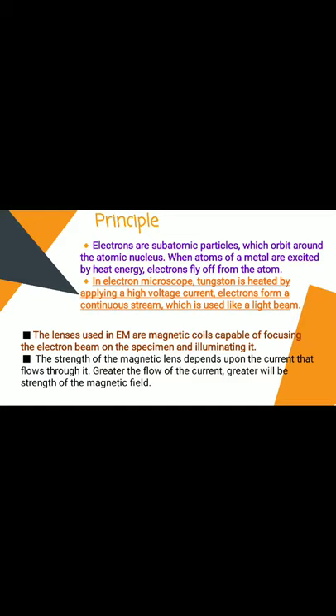The principle of the electron microscope: electrons are subatomic particles that orbit the atomic nucleus. When atoms of metal are excited by heat energy, electrons fly off from the atom. In an electron microscope, tungsten is heated by applying a high-voltage current, and electrons form a continuous stream, creating a beam. The lenses used in electron microscopes are magnetic coils capable of focusing the electron beam on the specimen. The strength of the magnetic lens depends on the current flowing through it — greater current means greater strength of the magnetic field.